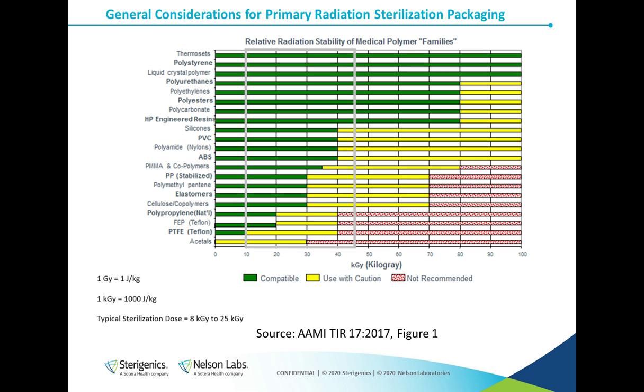The kilogray is the unit we use to measure the absorbed energy in material, with 1 kilogray being equivalent to 1,000 joules per kilogram of material. Typically, in radiation sterilization, the minimum dose required for sterilization is on the order of 8 to 25 kilograys. And there would also be a maximum dose that would be imparted to the material, perhaps double the minimum dose, perhaps up to 45 or 50 kilograys typically.